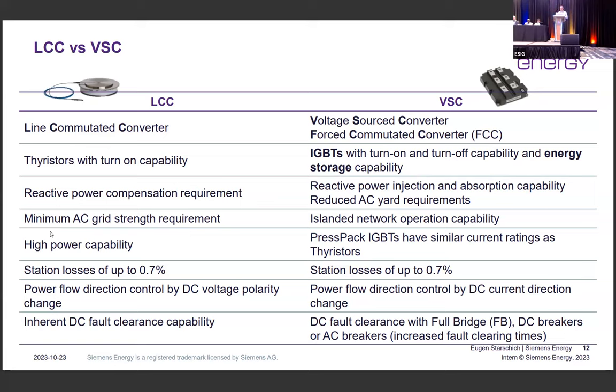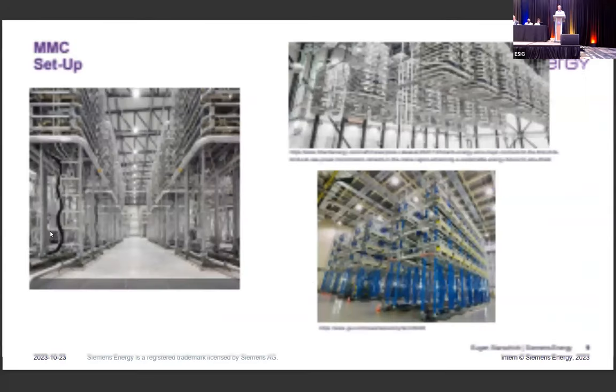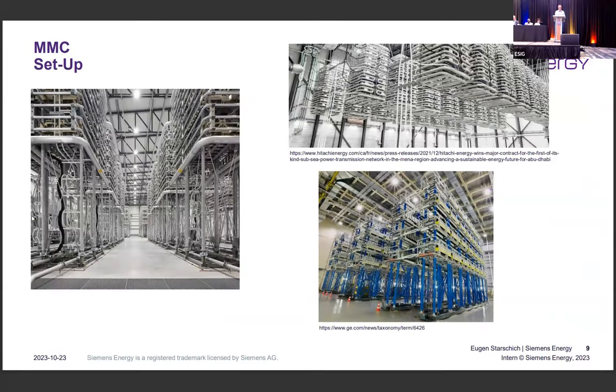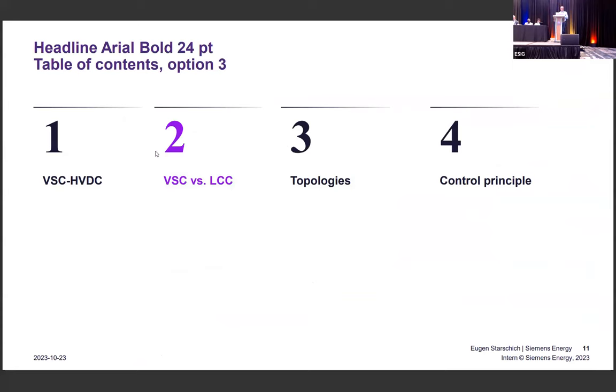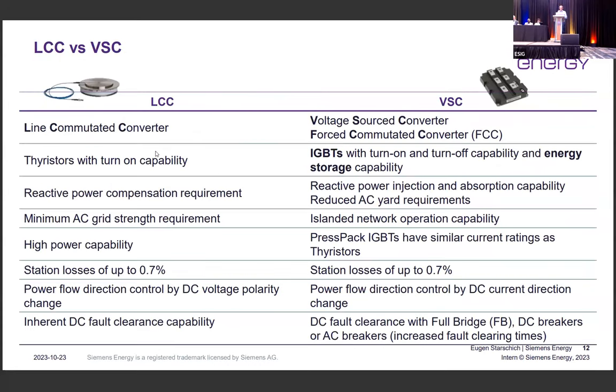If we look at the converter, looking at this setup, I would say 80% of the space required is for the capacitors, for the energy storage. So many of the features that we see in the VSC technology do not come only from the IGBTs, but especially also from the energy storage capability of the VSC converter. We don't need reactive power compensation. We can operate in a very weak network with the VSC technology, up to the islanded network.